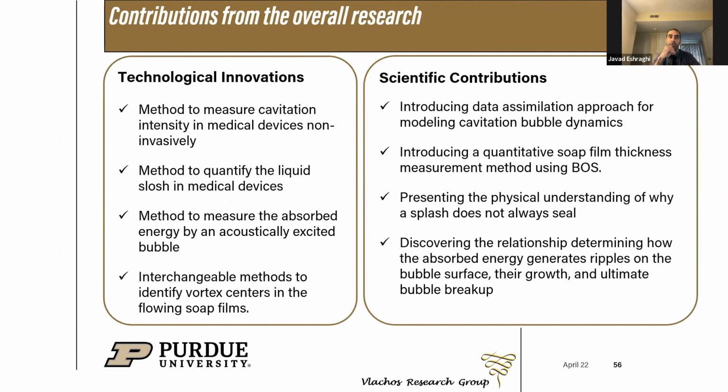Now let's summarize some of the contributions of the research that I presented. We developed a method to measure cavitation intensity in medical devices in a non-invasive way, methods to quantify the liquid slosh in medical devices, as well as a method to measure the absorbed energy by an acoustically excited bubble. Also, we introduced interchangeable methods to identify vortex centers in the flowing soap films.